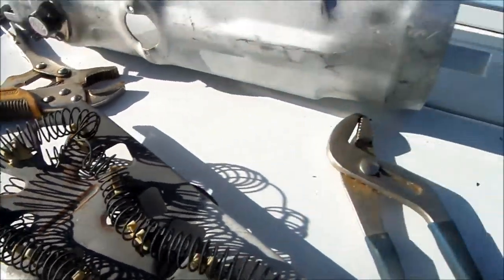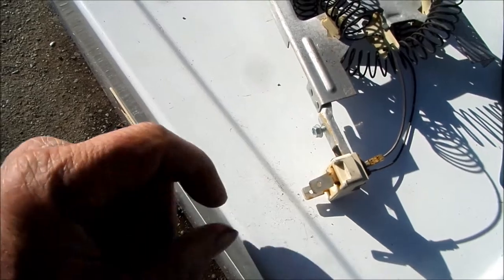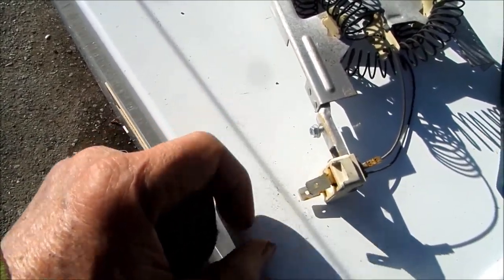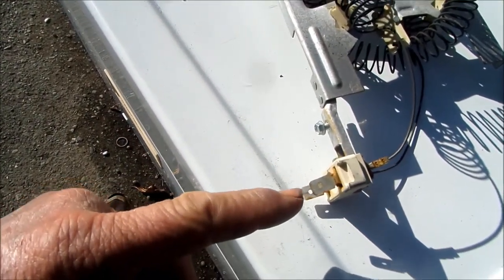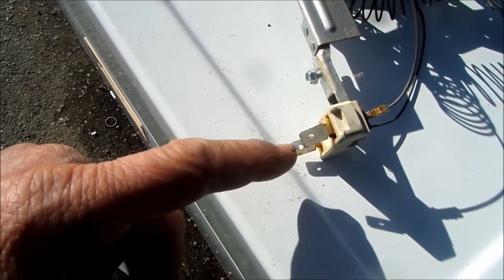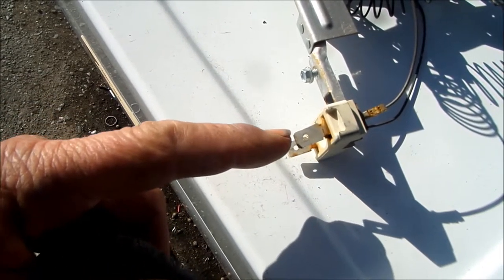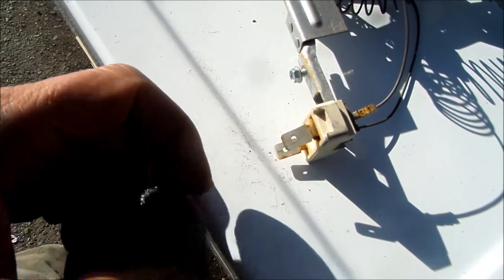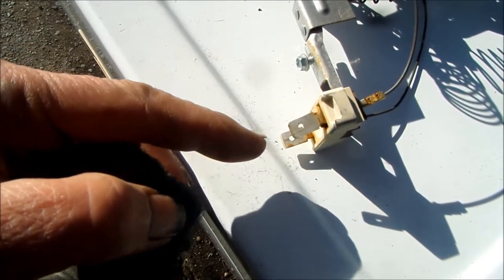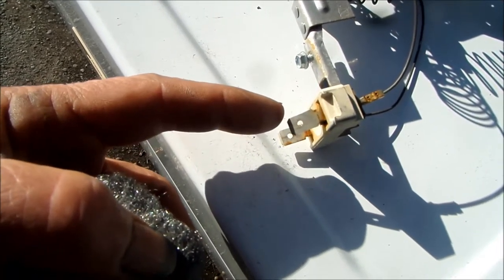So also we want to make sure that the terminals are clean here, and the spade connectors that go on are tight. Otherwise it would cause excess heat to build up on the terminals, and then normally it will toast the wire. So if you see a spade terminal that's hooked onto your terminal here that kind of looks burnt, that means basically the spade terminal is too loose for the spade here.